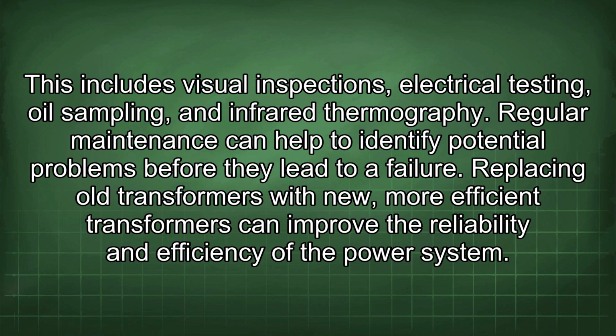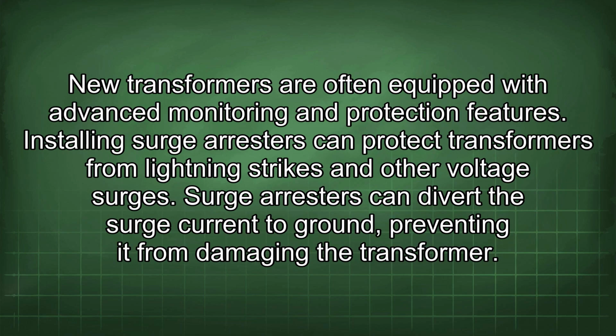Replacing old transformers with new, more efficient transformers can improve the reliability and efficiency of the power system. New transformers are often equipped with advanced monitoring and protection features. Installing surge arresters can protect transformers from lightning strikes and other voltage surges. Surge arresters can divert the surge current to ground, preventing it from damaging the transformer.